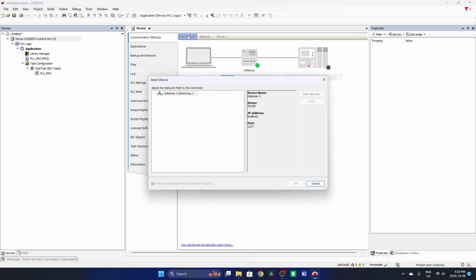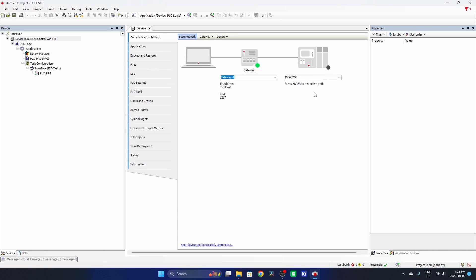And if I scan the network, I won't be able to find that PLC as an option. So that's an indication that your PLC is not running. You can't find it anywhere.